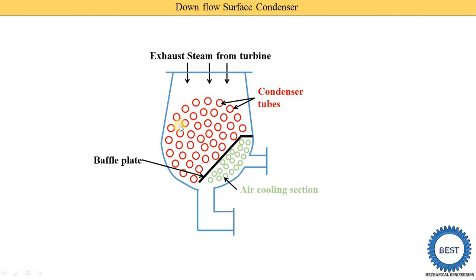In this diagram you don't see from where the cooling water enters. Cooling water is entered similar to the double pass surface condenser — I already made a video on that, and the link is provided in a card on the top right of your screen. The cooling water is supplied from the downside of the condenser, enters the tubes, moves upward, and then reverse flow of the water takes place from the top tubes. Steam passes outside the tubes and water inside, so heat is transferred from the steam to the water. Steam supplies heat energy to the water, starts to condense, and is collected at the bottom of the condenser, converting into liquid called condensate.